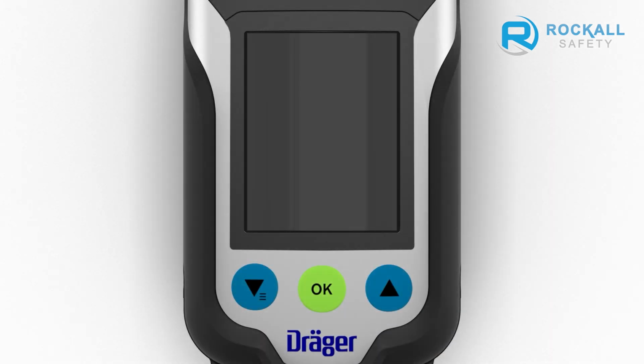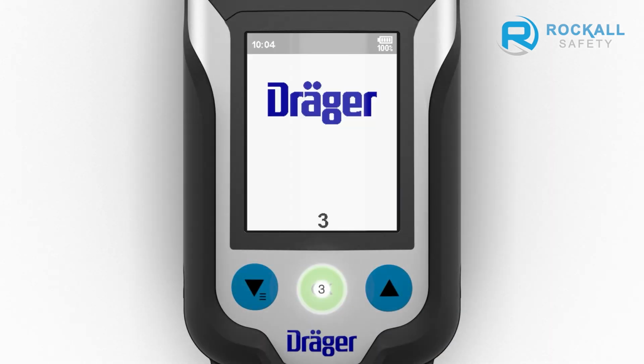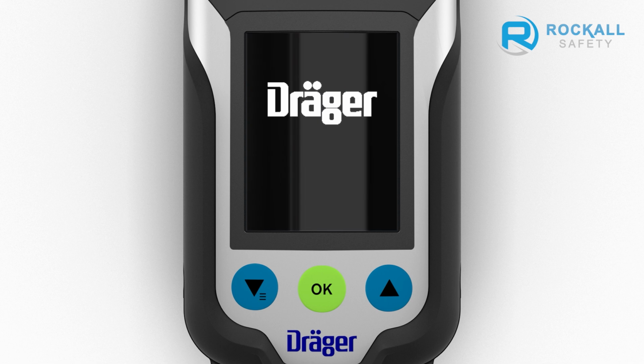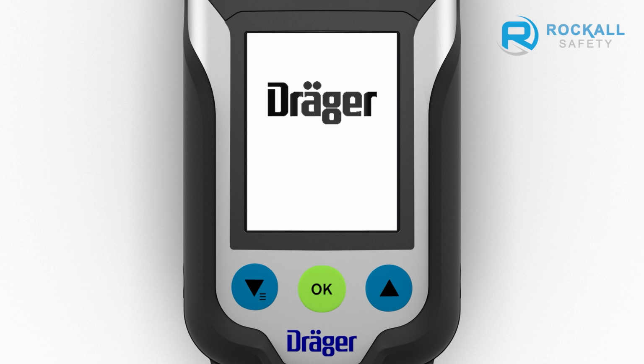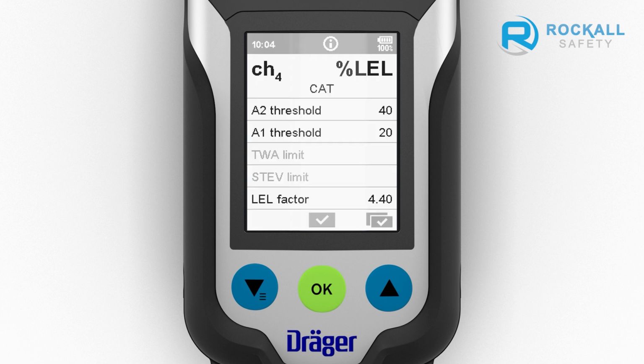The X-am 8000 is turned on by pressing the green OK button for 3 seconds. Once successfully turned on, the device performs the following actions. The display shows the startup screen and the current software version. A self-test is then run. Once successfully started, the LEDs flash, an audible signal sounds, and the vibration alarm is activated. There is the option of displaying a customized information screen. After that, the alarm thresholds and any expired intervals, for a bump test or a calibration for example, are displayed.